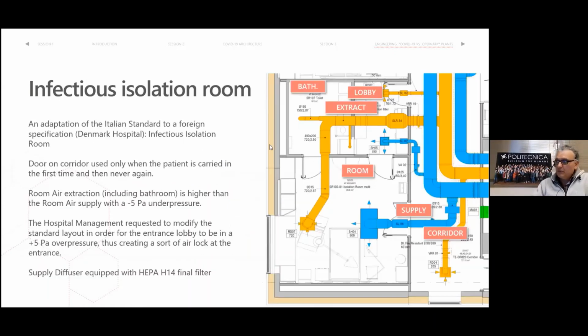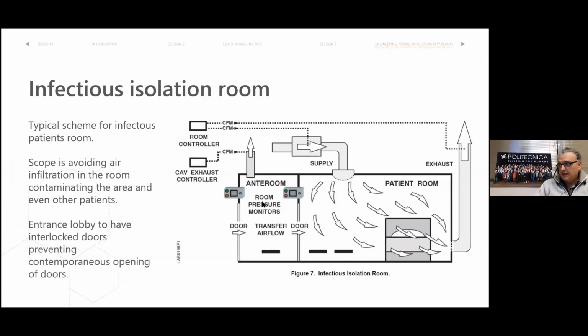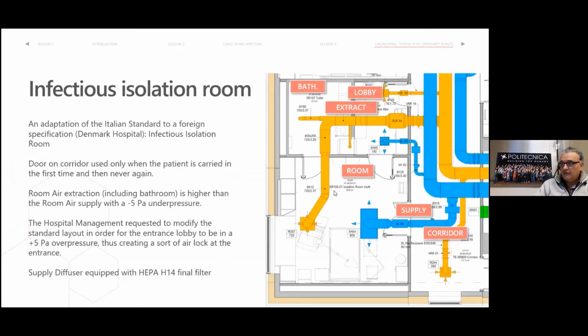If we go ahead, this is an example that we applied in one of our hospitals. In this case, there is a difference with respect to this scheme. As you see here, the anteroom is at an intermediate pressure, but in this case, the medical staff of the hospital asked us to provide the lobby, this lobby or anteroom, as you like, not at the intermediate pressure, but at a higher pressure, just like an airlock. Because when you provide an airlock, you have a pressure which is higher than all the rooms outside, all around. And so in this case, we have minus 5 Pascal in the room, this is the room where there is a patient, and plus 5 Pascal in this airlock. So we are very, very sure that there is no infiltration from this room to the airlock and then to outside.